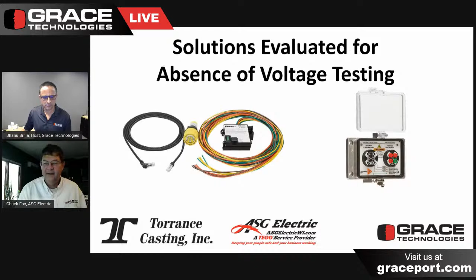Two other big requirements: as we studied the specifications, we have a Category 4 rating at 575 volts for that furnace on the shop floor. Given the rated values of the specifications, the Panduit product did not qualify to be used in that application, it was outside of their specifications.